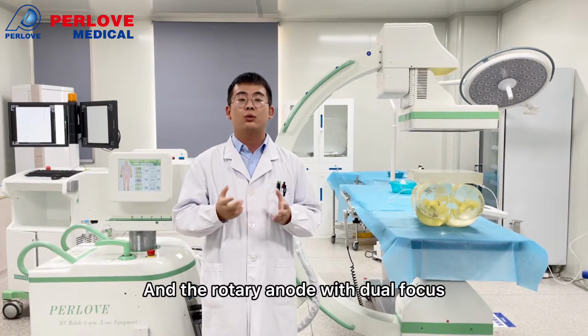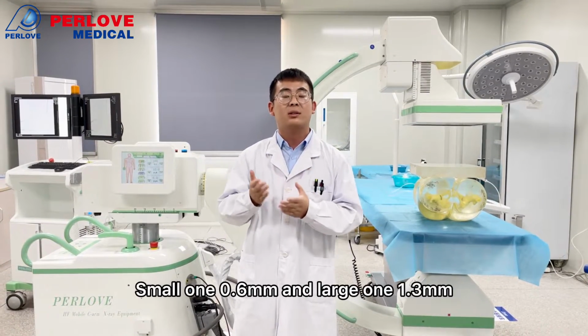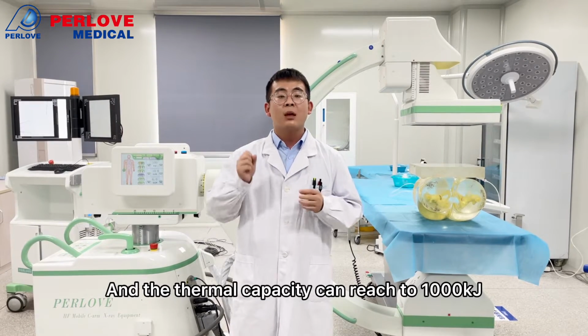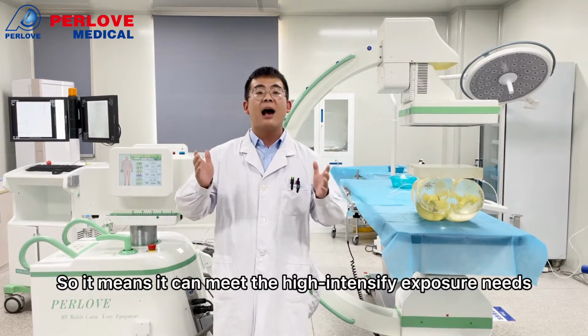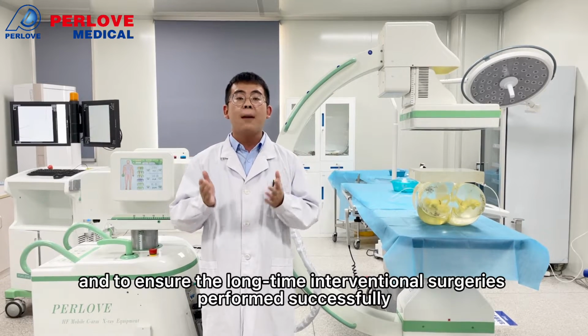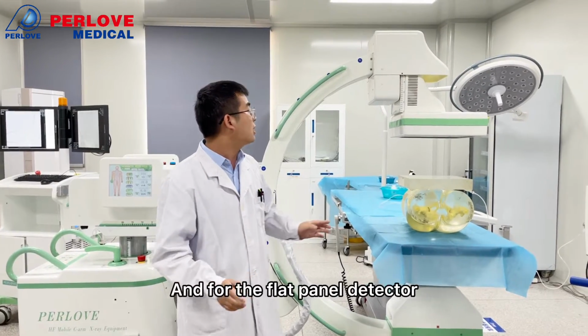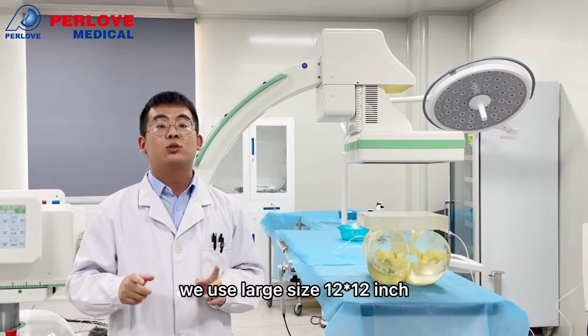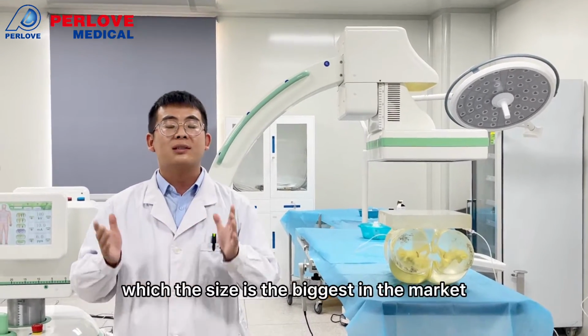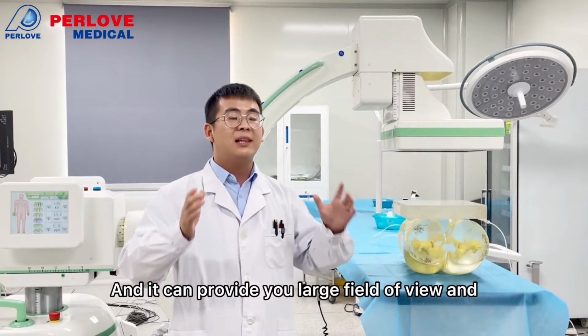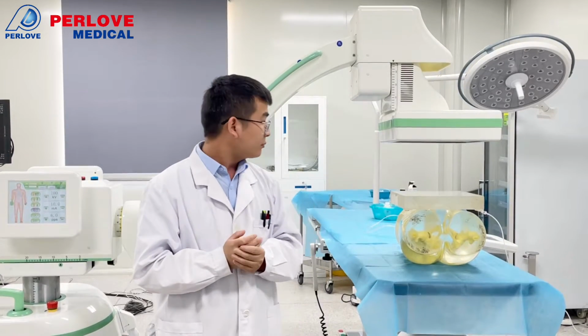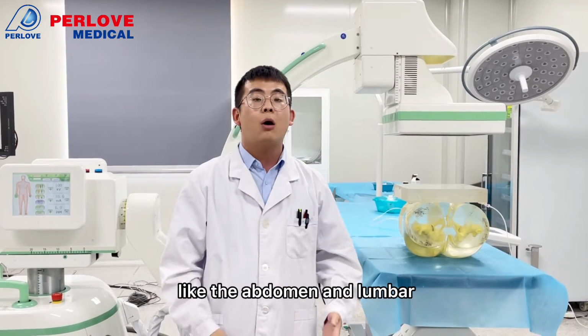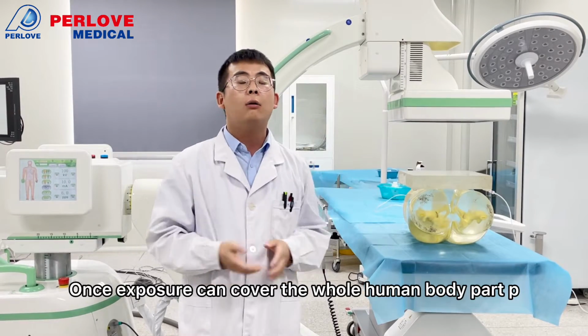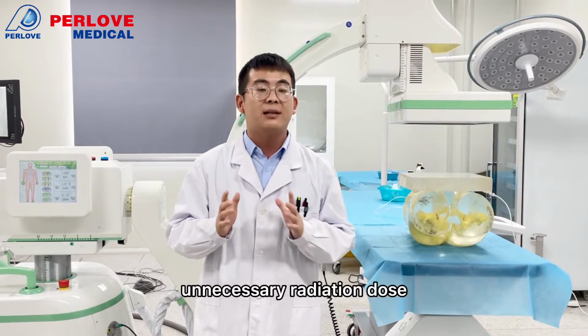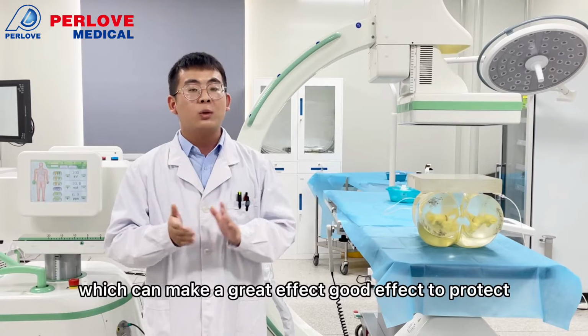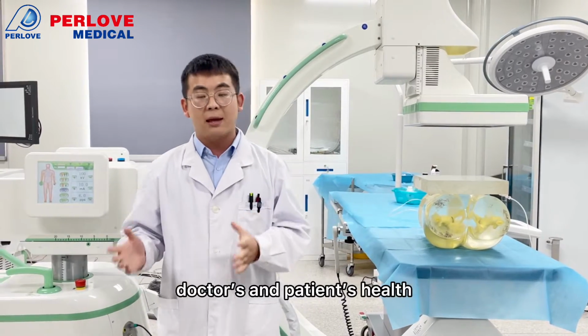And the rotary anode has a dual focus, the small one 0.6 and the larger one 1.3 millimeters. The thermal capacity can reach 1000 kilojoules, so it can meet high-intensity exposure needs and ensure long-time interventional surgeries are performed successfully. For the flat panel detector, we use a large size 12 x 12 inch dynamic flat panel detector, the biggest size in the market, which provides a large field of view and the best quality images. For large body parts like the abdomen and the lumbar, one exposure can cover the whole body part, so it can reduce the unnecessary radiation dose caused by repeated exposure, which helps protect doctors' and patients' health.